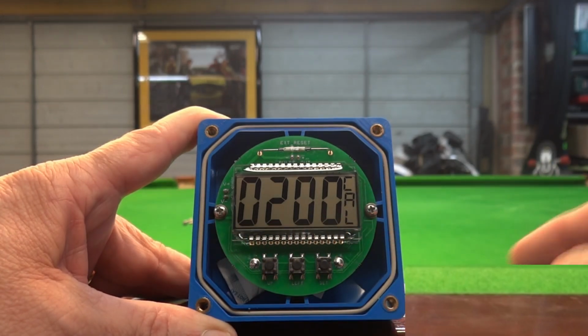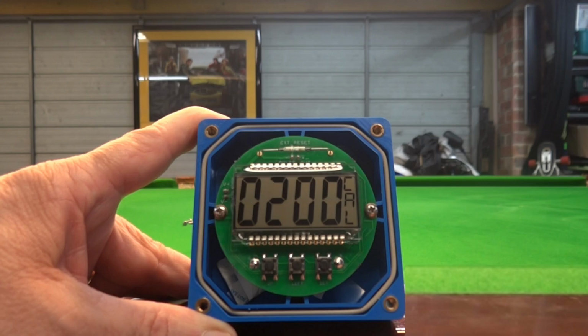Now, let's suppose the user has carried out a volume test of this flowmeter by filling up an IBC with 1000 liters. Let's call this the actual volume. However, it was noted that the flowmeter reading was 1100 liters. So in this first example, the flowmeter in effect is reading approximately 10% high.